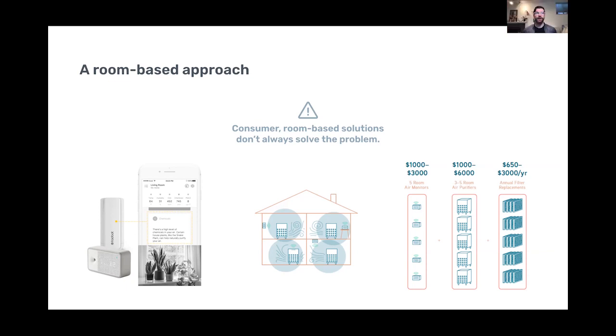Yeah, disclaimer, we're not a ventilation manufacturer. We're not experts on that. From what I have learned, the enthalpy core of an ERV is going to recover not only some heat, but it's also going to recover some total energy or enthalpy across the ventilator, meaning your total output of a heating and cooling system, for example, is not only the sensible change, so the change in what we feel in terms of temperature, but the latent, and the latent being the amount of moisture.